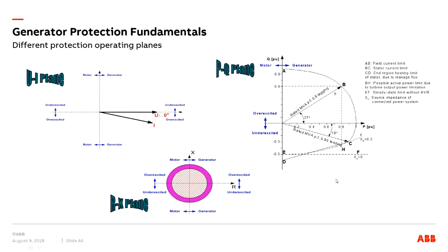Okay. So the rest of the protections are based on these different planes. There are 3 different planes considered for protection operation. One is the UI plane, or the VI plane, generally used for generators rated with power factor 0.8 or 0.95, depending on the machine design. The PQ plane is used to determine the generator capability curve, and the RX impedance plane is used for deriving loss of excitation, pole slip, and under impedance protections. Okay, so as you can see, depending on the excitation situation, the machine can act as a generator and a motor.